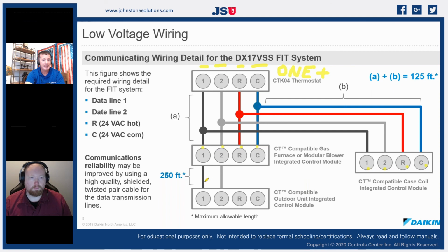But we notice, go into the outdoor unit. We do not require any more than 2 wires go into the outdoor unit, number 1 and number 2, because our outdoor unit has its own power source, right? It's hooked up to our 230-volt single phase outside. So there is no connection between common or ground between the indoor units and the outdoor units. So we have to make sure that we have a properly grounded outdoor unit, because that ground is going to be the key to make these things successful.